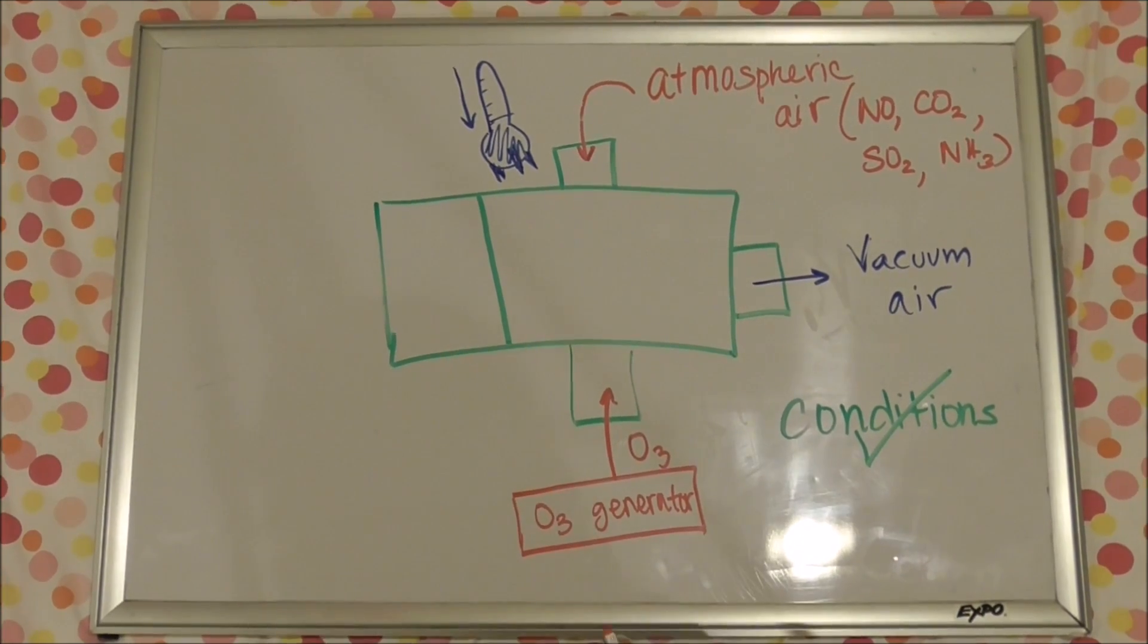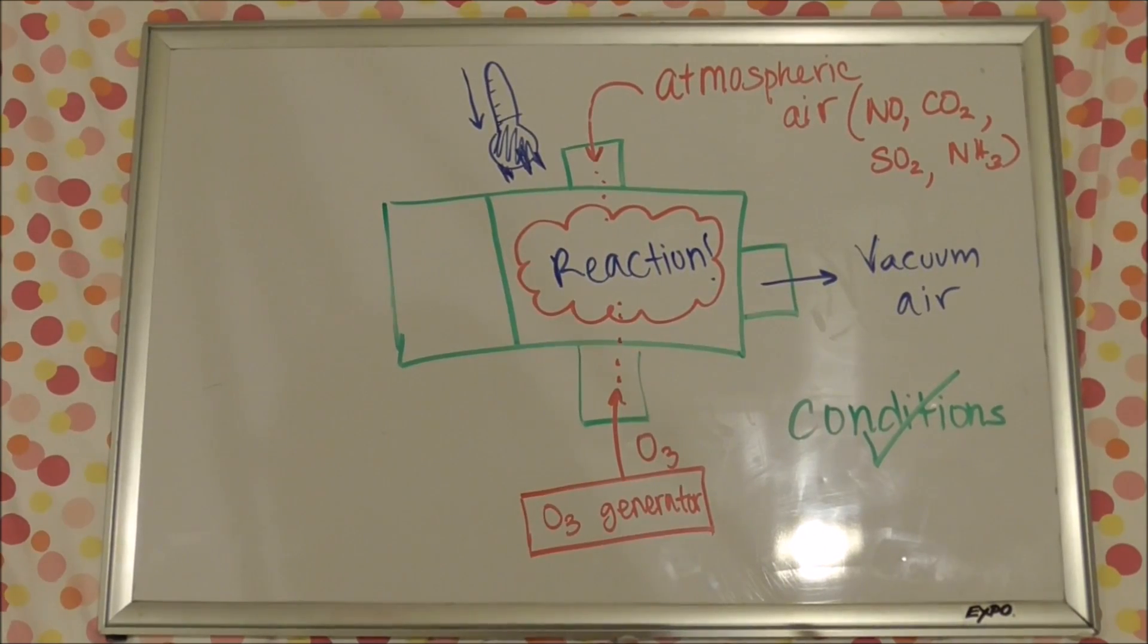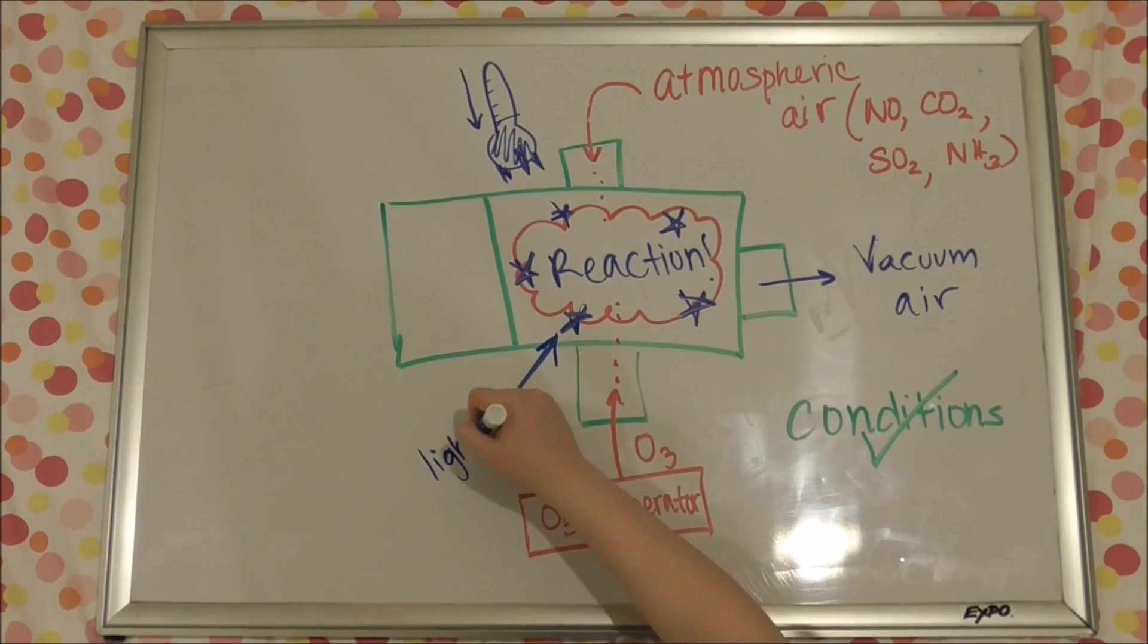What happens next is basically the O3 flows in and the atmospheric air flows in. And in the reaction chamber, the NO reacts with the O3 in order to create NO2 in an excited state, which will also produce light later.